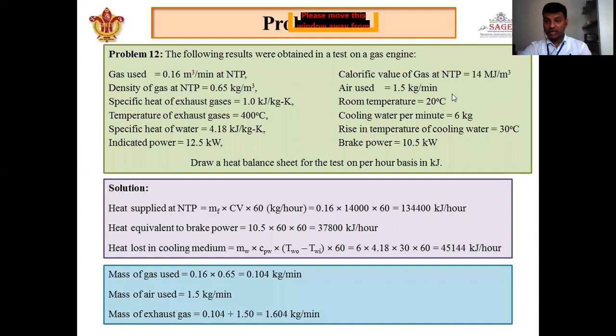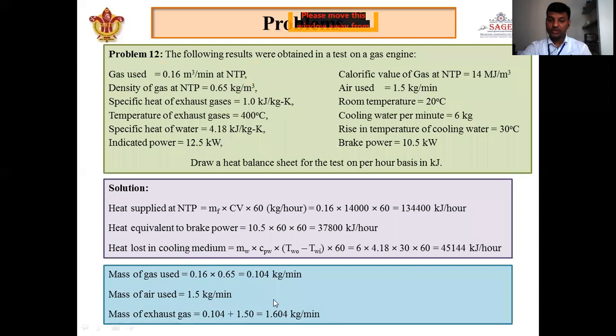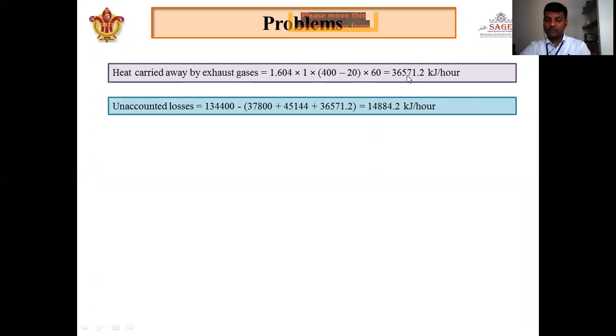Heat carried away by exhaust gas = mass of exhaust gas × Cp × ΔT × 60. Mass = 1.604 kg/min, Cp = 1 kJ/kg·K, ΔT = 400 − 20 = 380°C, multiplied by 60 to convert to per hour. This gives 36,571.2 kJ/hour as the heat carried away by the exhaust gases.